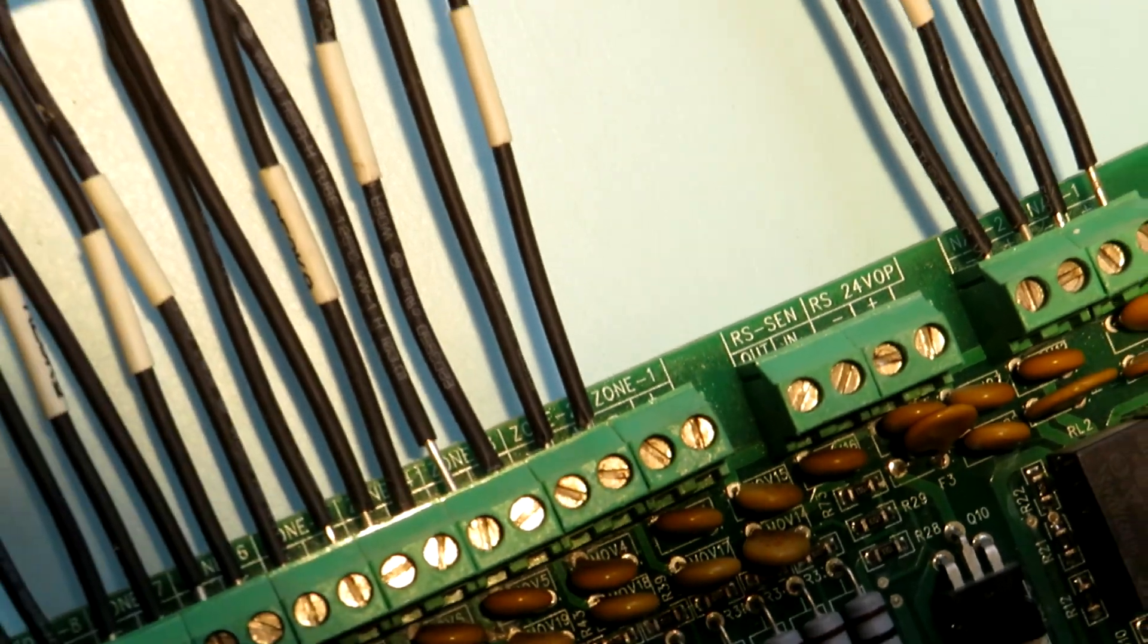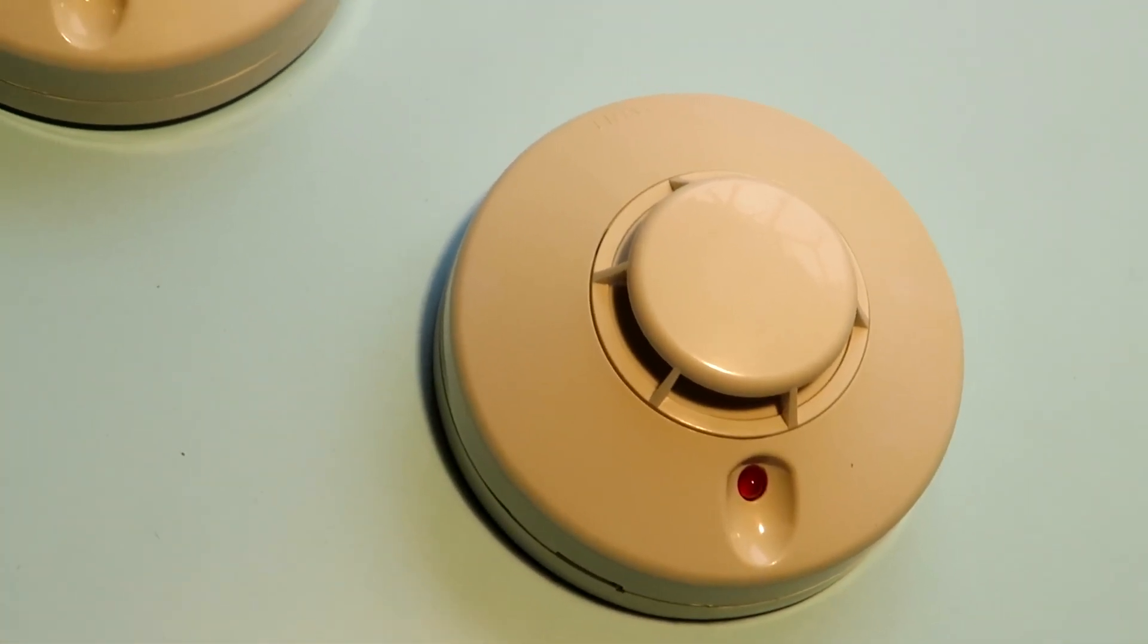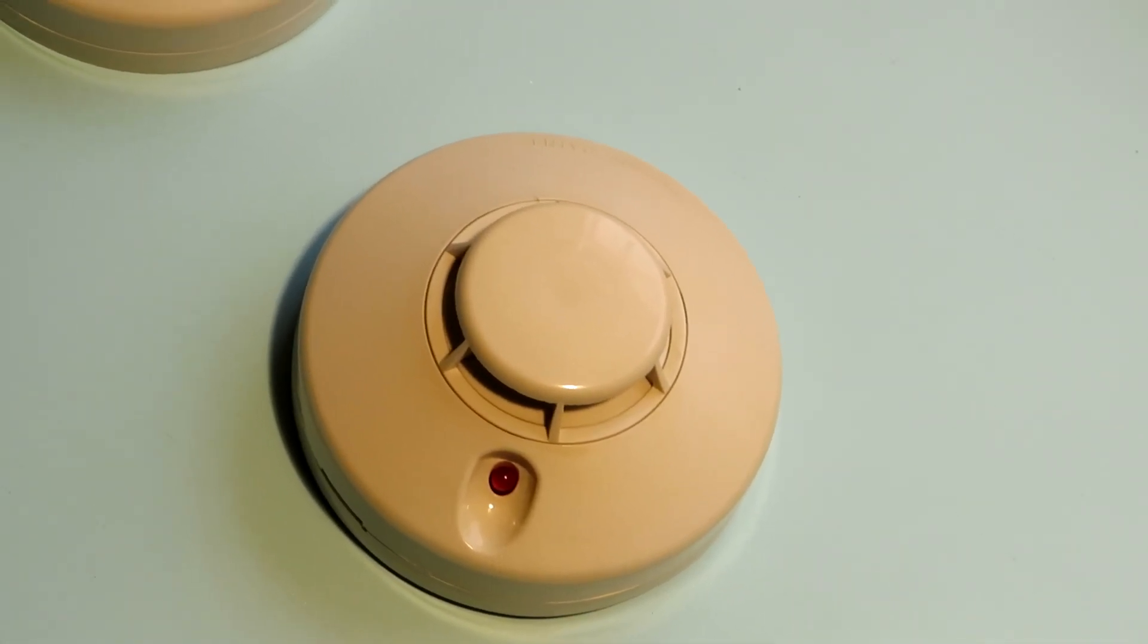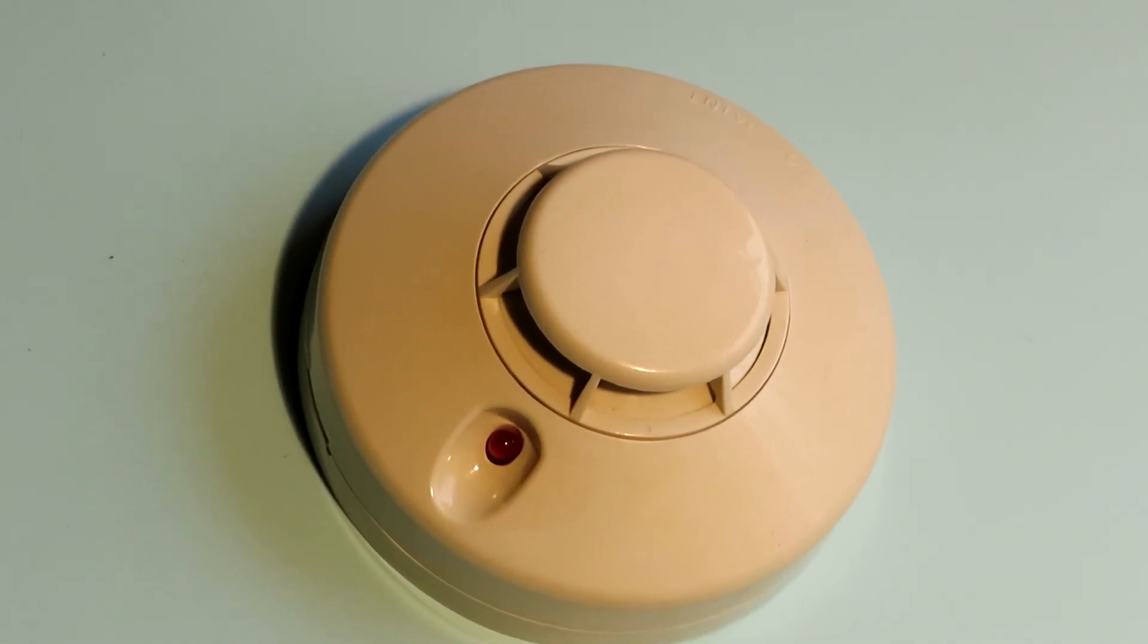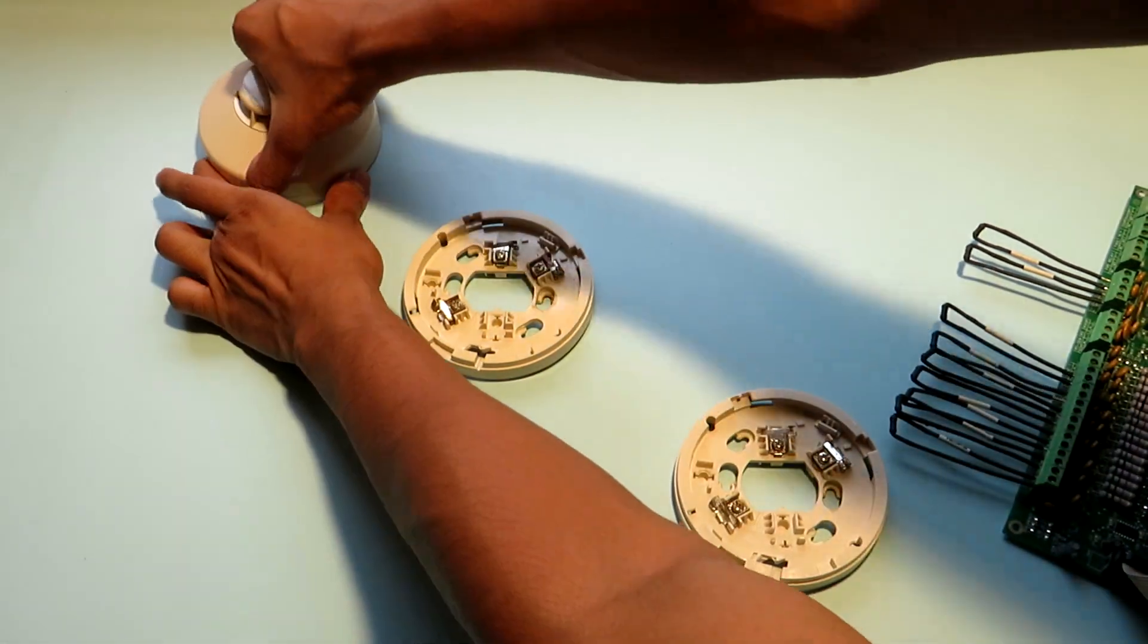You can see here our cables will first come from the panel and enter the first detector then get looped as per the schematics to the second detector which will further get looped to the third detector and the EOL resistor will be installed in the third detector. Now I'll detach the smoke detectors from the base units so that we can make our connection.